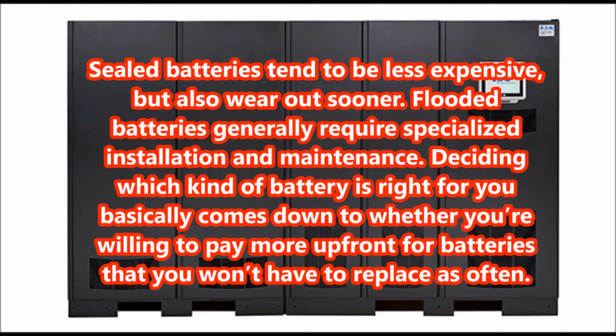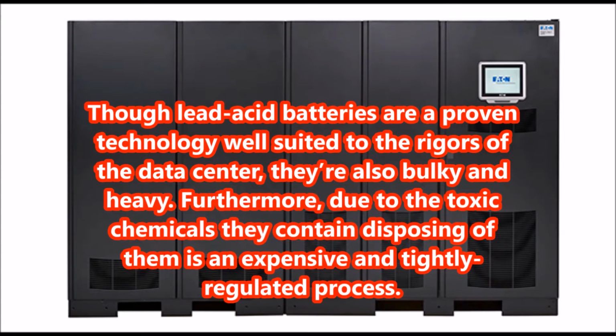Sealed batteries tend to be less expensive but also wear out sooner. Flooded batteries generally require specialized installation and maintenance. Deciding which kind of battery is right for you basically comes down to whether you're willing to pay more upfront for batteries that you won't have to replace as often. Though lead-acid batteries are a proven technology well suited to the rigors of the data center, they're also bulky and heavy. Furthermore, due to the toxic chemicals they contain, disposing of them is an expensive and tightly regulated process.